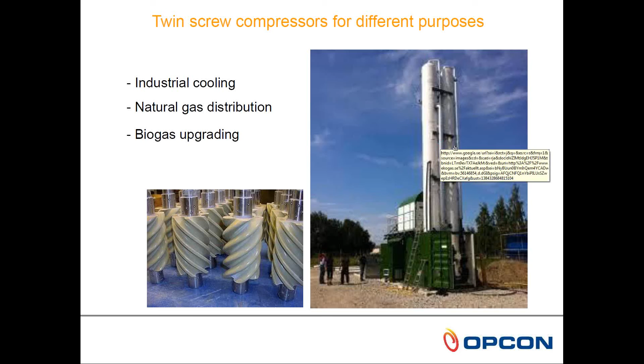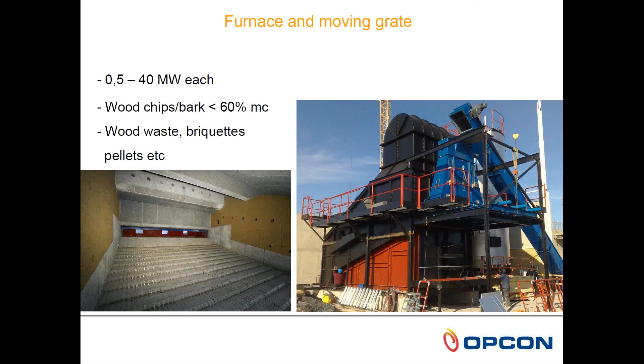We are doing combustors as well for biofuels, for example, like wood, chips, and bark. We can combust material with a moisture content up to 60%, very wet fuels, in this combustor. It's a great combustor, a moving grate combustor. We can also use wood waste, for example, or briquettes, pellets, etc. So this combustor is then combined with a boiler for hot water, for steam, for thermal oil, or for some other purpose. And we do them in sizes from 500 kilowatt up to 40 megawatt each.